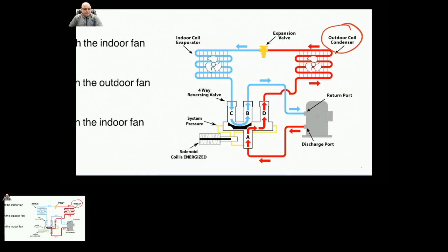So the question is, would there be an issue of piping expansion and contraction in the defrost cycle? Yes, it would be. And that's a very good question. Thank you, Sam. When it is like -20 Fahrenheit outside, and you're heating those pipes up to 140, well, you can't do that. But let's say you're sending them to plus 50, 60 degrees Fahrenheit.